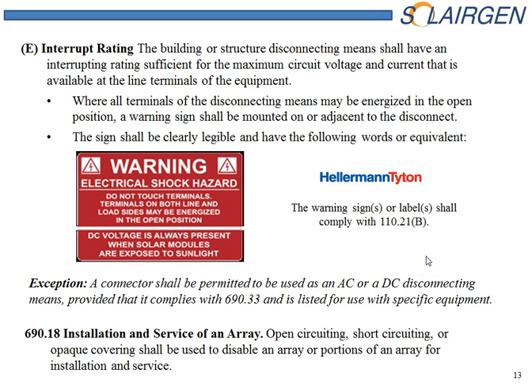So it has to relate to the inverters that it's disconnecting. This warning label is only required where the terminals are actually accessible. This kind of goes along with the arc flash warning. If you can access these labels, whether it's residential or commercial, and work on them, you must have a label indicating that the terminals are live and may be energized.